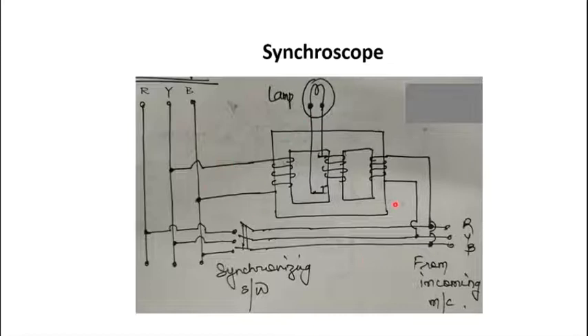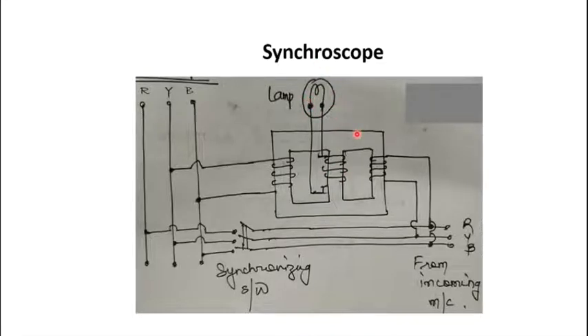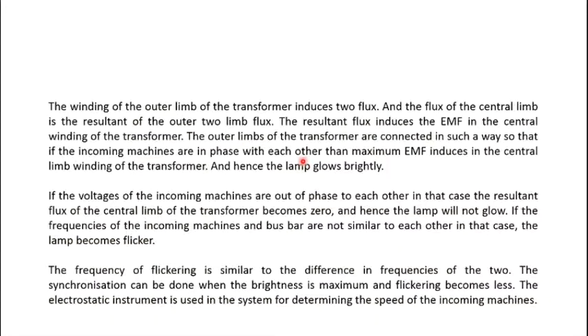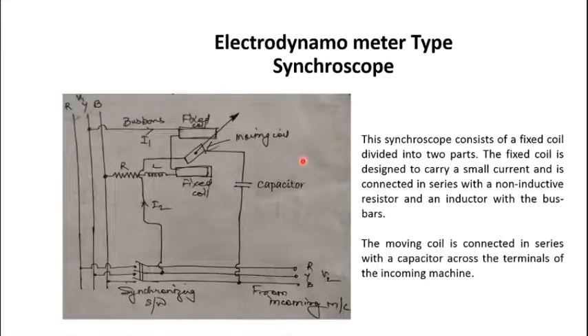If one source is faster and the other slower, the lamp will flicker because the rate of change is not exactly 50 Hz, indicating a phase difference. However, this conventional synchroscope cannot tell us which source is faster and which is slower — that is its limitation.